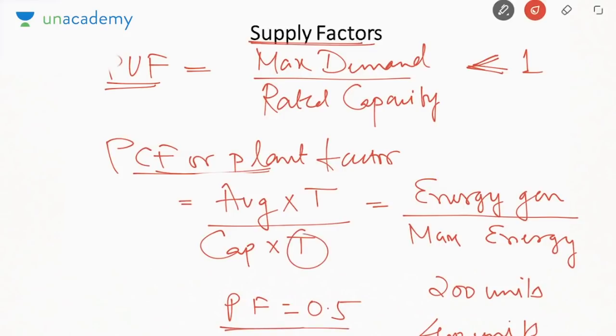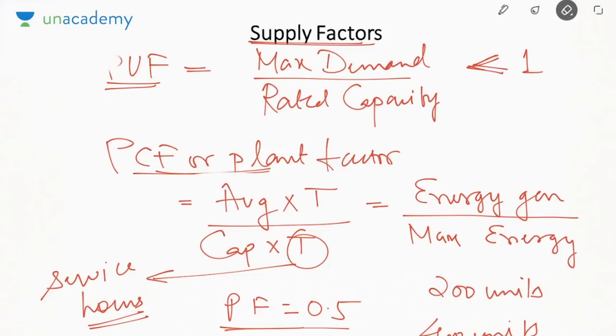This T is called service hours. Service hours means for how much duration the plant is working, because it will be down for some duration for maintenance purposes. So you have to take care that the actual energy generated is average demand into the number of service hours, whereas the maximum energy that could be generated will be based on capacity. That is, if the plant was working on full load during that entire duration, then it would be able to generate more power. That is your plant capacity factor or plant factor.